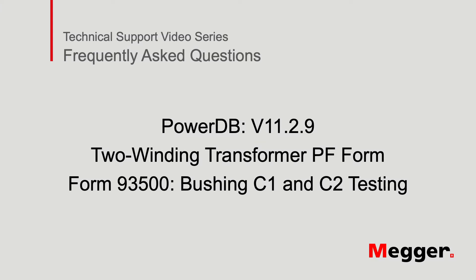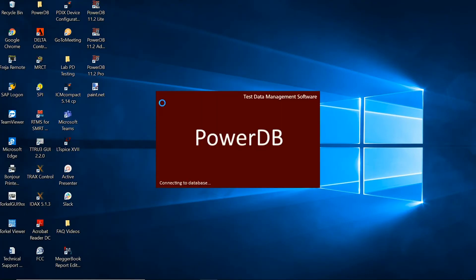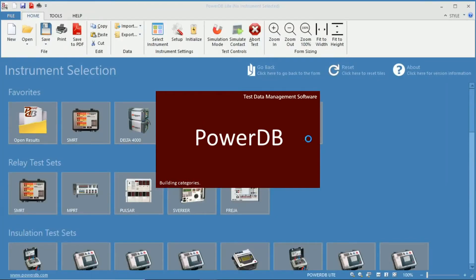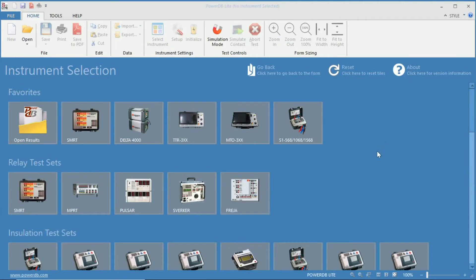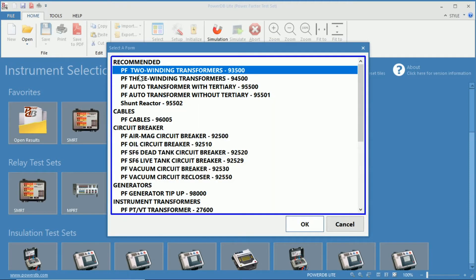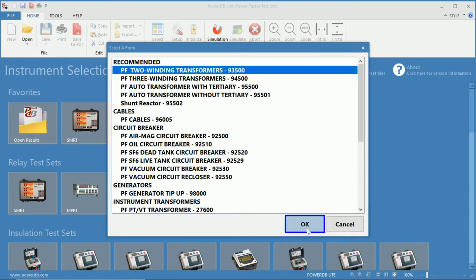Hello and welcome to Megger's Technical Support videos, where today we will be discussing the Power Factor Form 93500 Bushing C1 and C2 tests. The first step is to open up the appropriate PowerDB software — in this case PowerDB Lite version 11.2.9. Once the PowerDB software is opened, you can select your instrument from the list. We will be using the Delta 4000 Power Factor test set, using the Power Factor 2 Winding Transformers 93500 form.